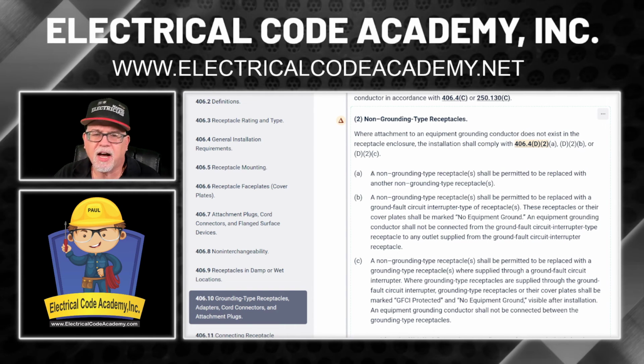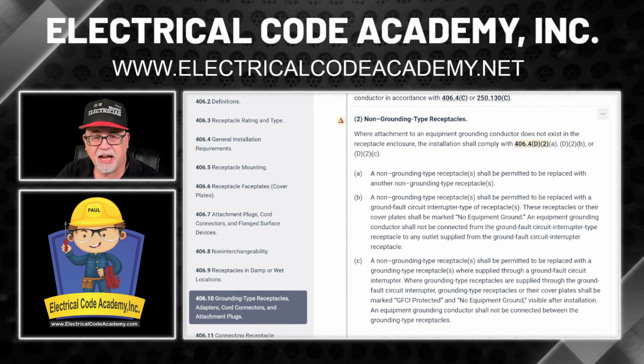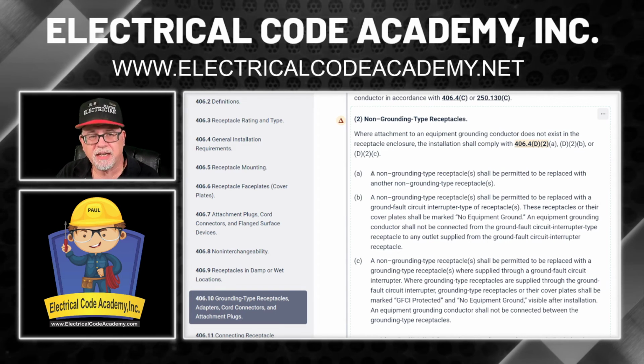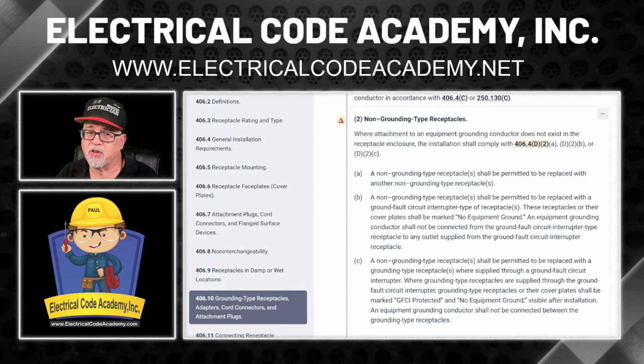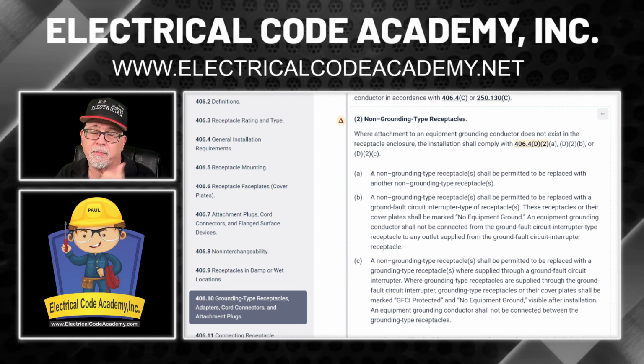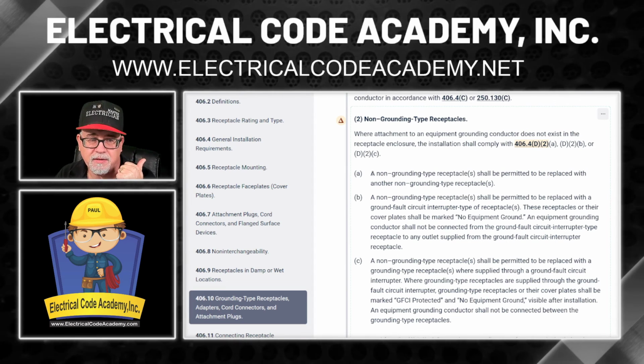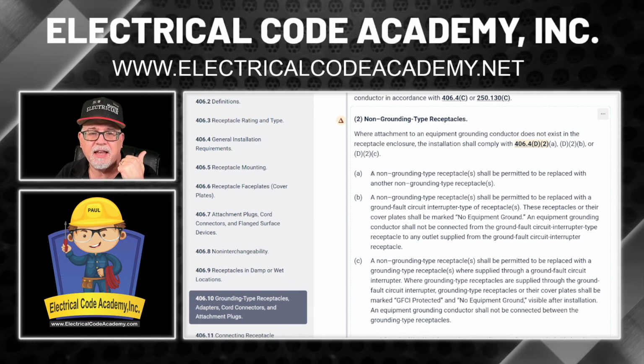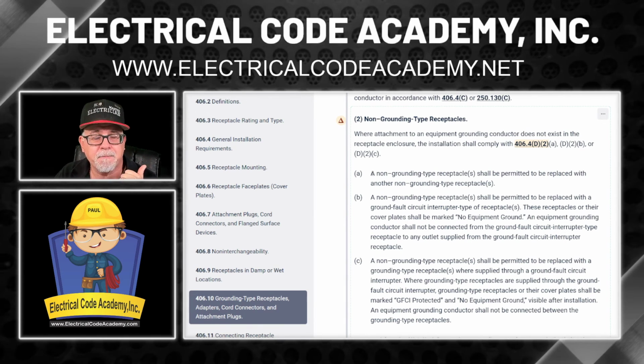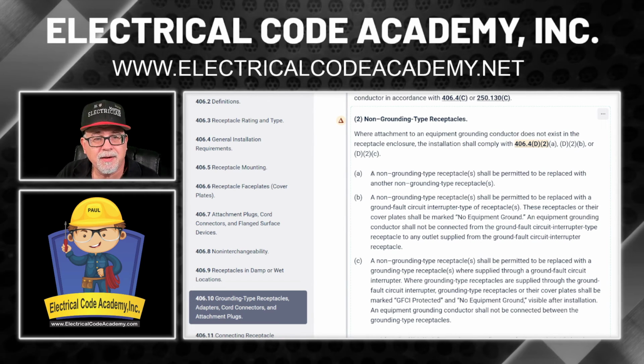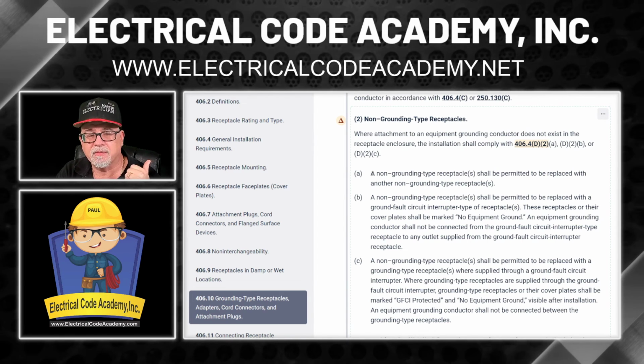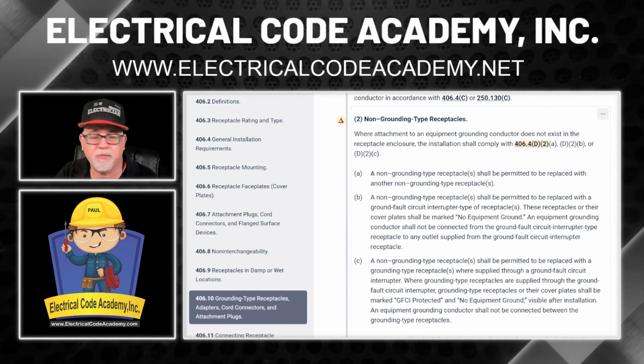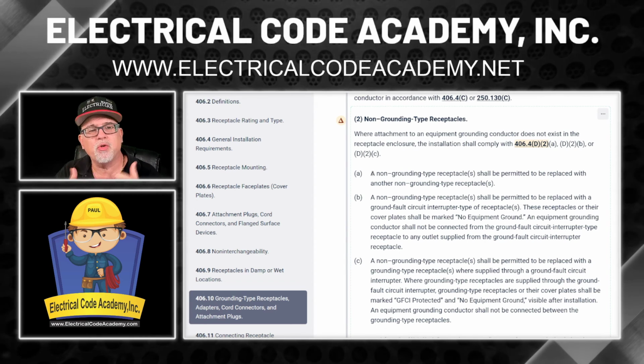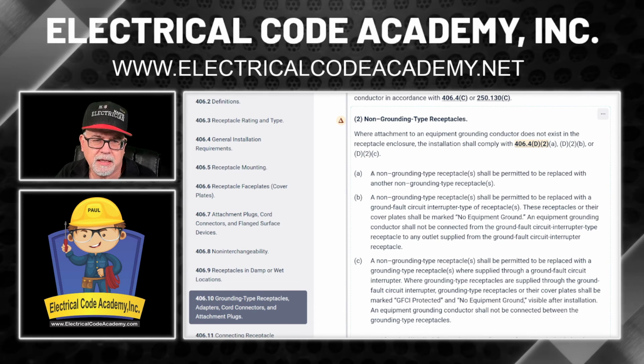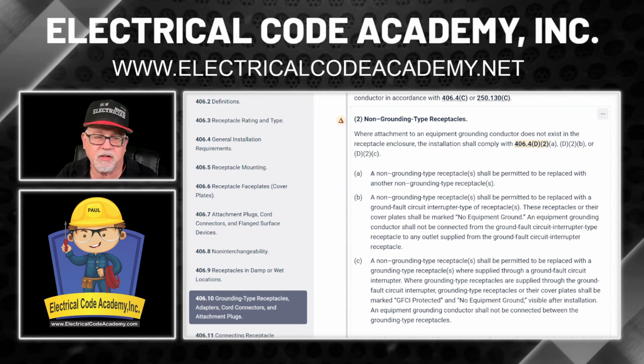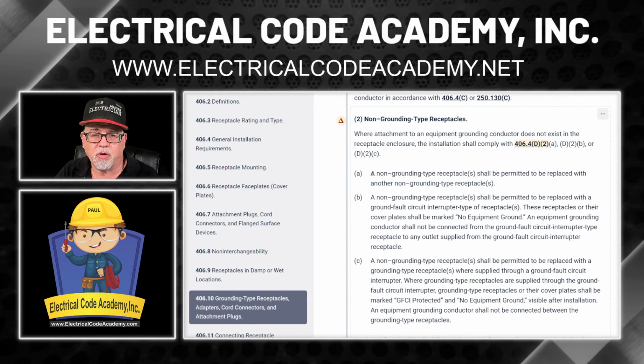Now, one of the other options that you have here is item C. And that is, you could have installed, like we said earlier, the GFCI circuit breaker if the panel can accept one. Okay, so maybe you had an upgrade. And then all receptacles downstream from that are considered protected by the GFCI feature, right? There is still no equipment ground. There is no effective ground fault current path. But you do have this level of leakage current protection afforded you by the GFCI device. It's better than nothing, okay? So that's what you're doing here.